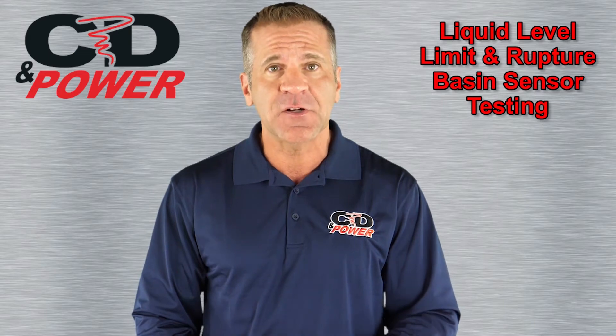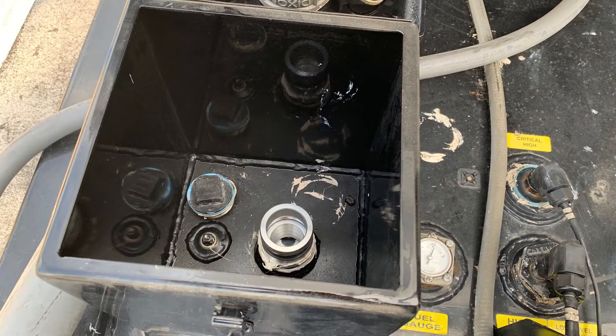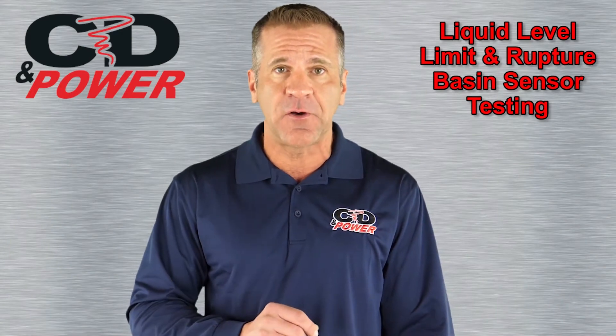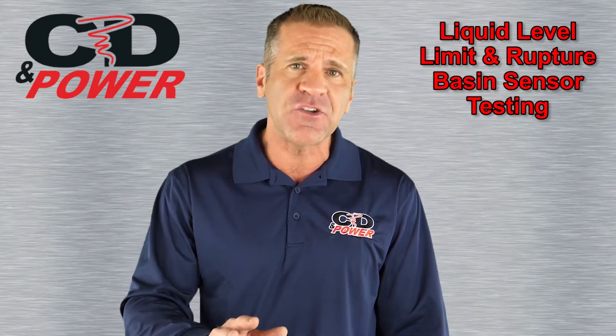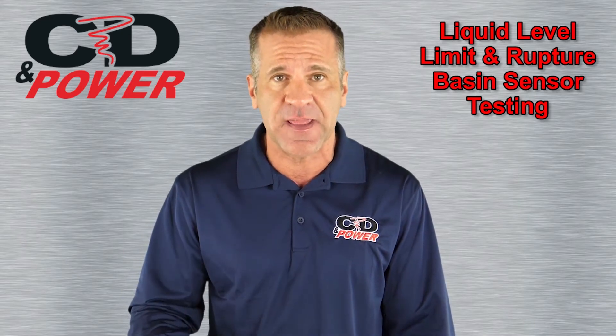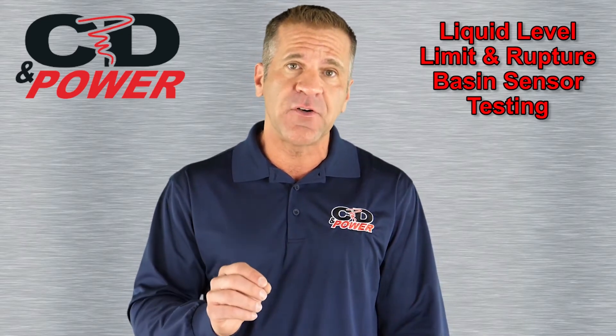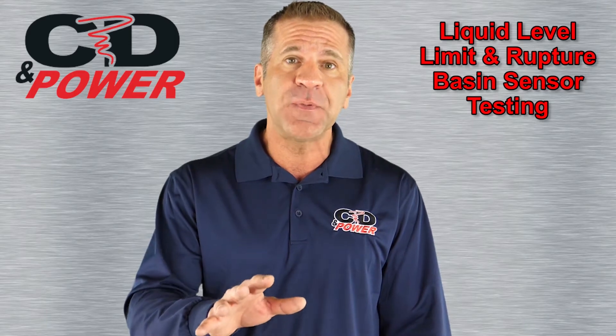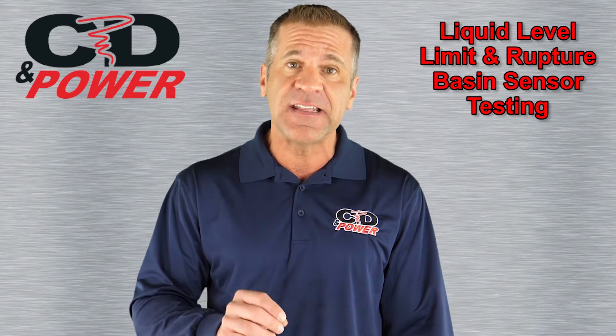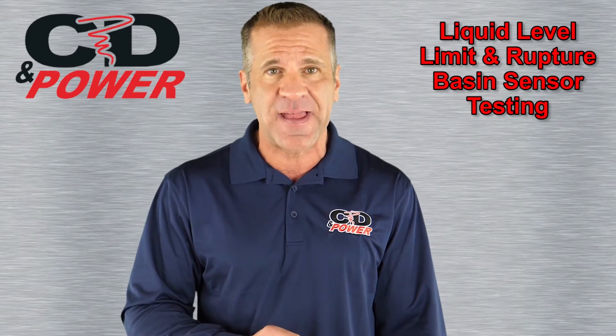One type of sensor is called a liquid level limit control. It's designed to make it impossible to overfill the tank. This device will: one, warn the operator when the tank reaches 90% full; and two, completely shut off the flow of fuel in time to prevent the tank from exceeding 95%. If fuel is delivered via a rigid hose, there must be a proper means for emptying the contents of the hose into the tank while still not exceeding 95% of the tank's capacity.